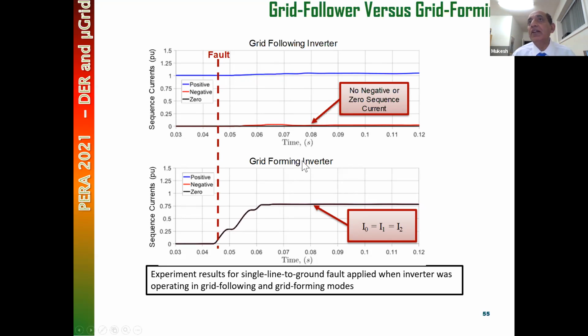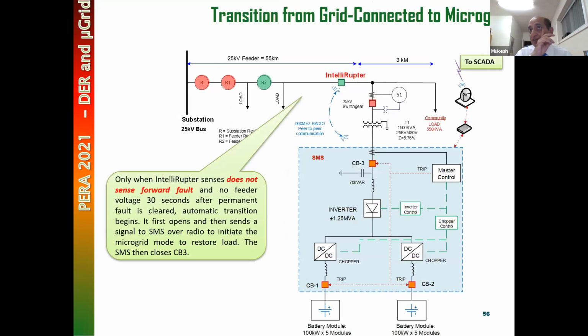But when it's operating in a grid-forming mode, it supplies positive, negative, and zero sequence current like a conventional generator. Not exactly like a conventional generator, I'll show you on one more fault record. I'm going to show you a little bit more. First, how does the transition happen?